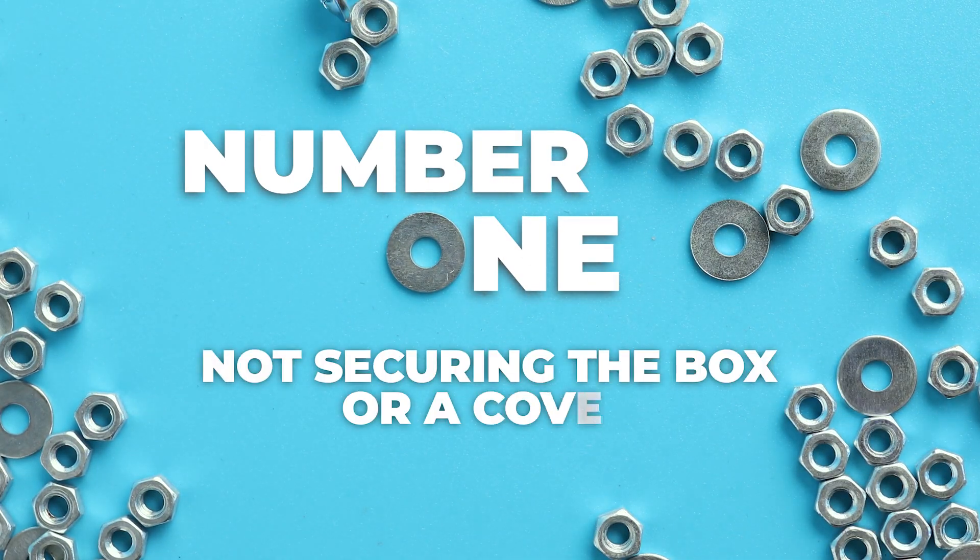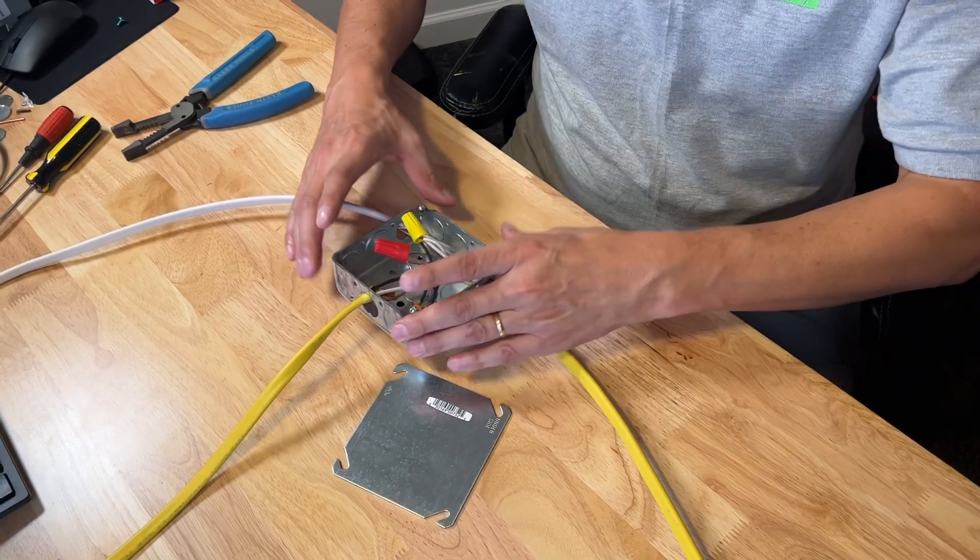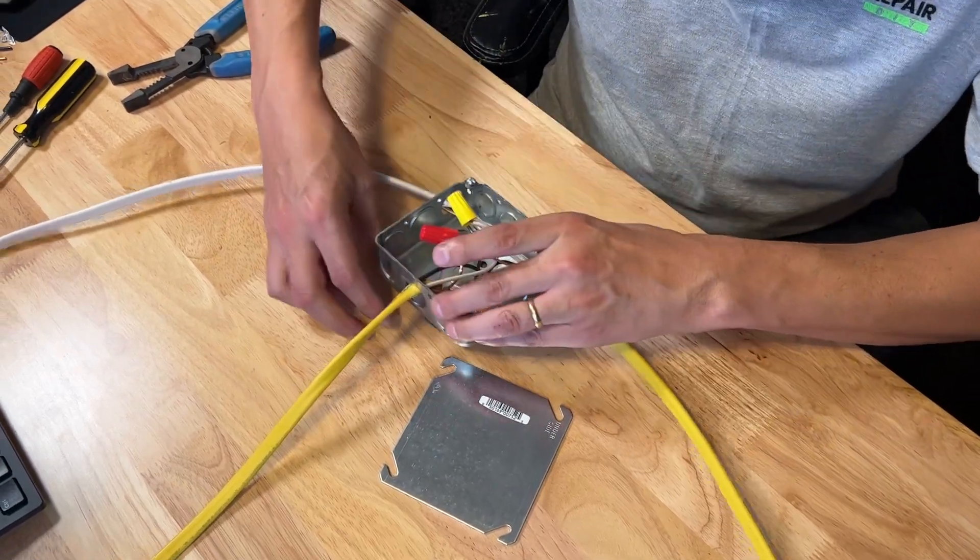Number one, not securing the box or a cover. So your electrical boxes, whether plastic or metal, but metal is far superior, far stronger, will last longer. And you definitely want metal if you're installing something heavy, like a ceiling fan, but they are required to be fastened. So they have to be screwed down and fastened to wood framing. So remember to screw your boxes down.